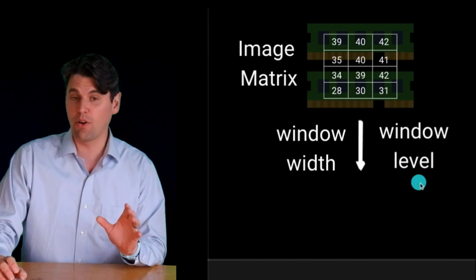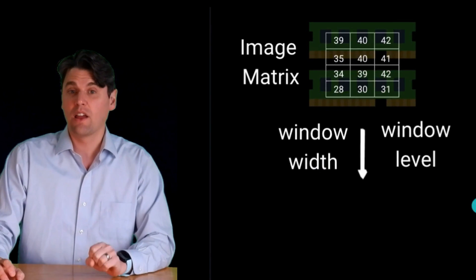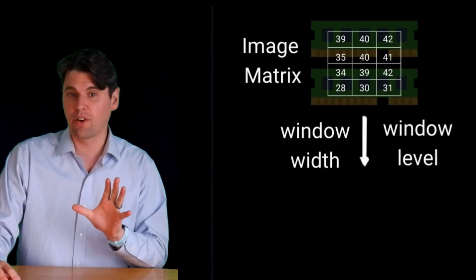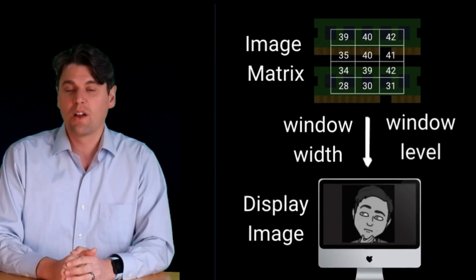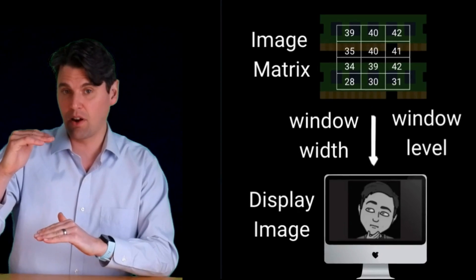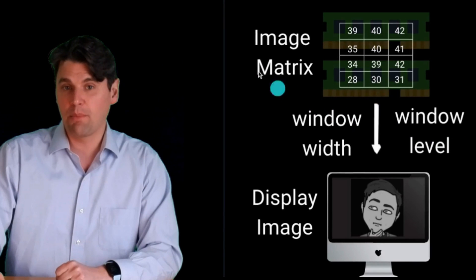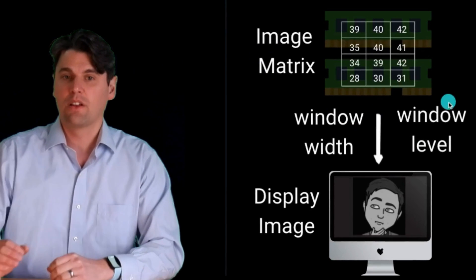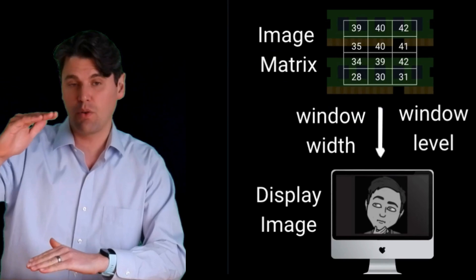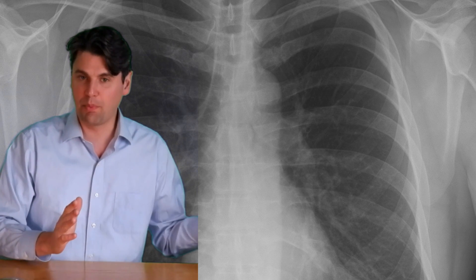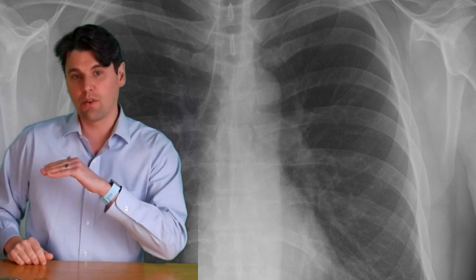The computer keeps that matrix stored, and then depending on the window width and window level that you select, you're going to have a different image displayed to the actual monitor. On standard monitors there are 256 shades of gray, so the values are going to be mapped from Hounsfield units to a scale from 1 to 256. If you have a really expensive mammography display it might have significantly more — from 1 to 1024.